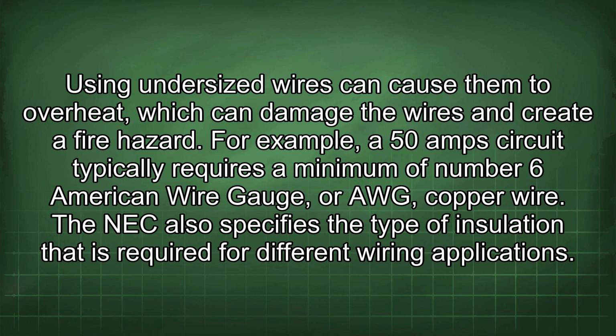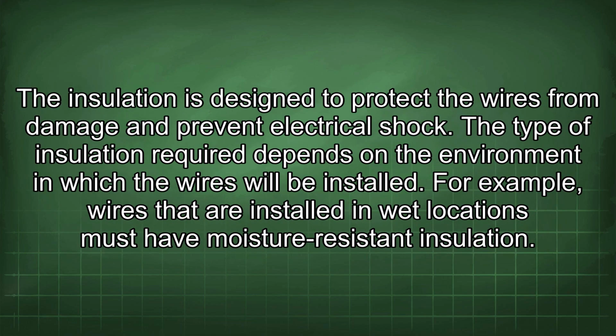Using undersized wires can cause them to overheat, which can damage the wires and create a fire hazard. For example, a 50-amp circuit typically requires a minimum of number 6 American wire gauge, or AWG, copper wire. The NEC also specifies the type of insulation that is required for different wiring applications. The insulation is designed to protect the wires from damage and prevent electrical shock. The type of insulation required depends on the environment in which the wires will be installed. For example, wires that are installed in wet locations must have moisture-resistant insulation.